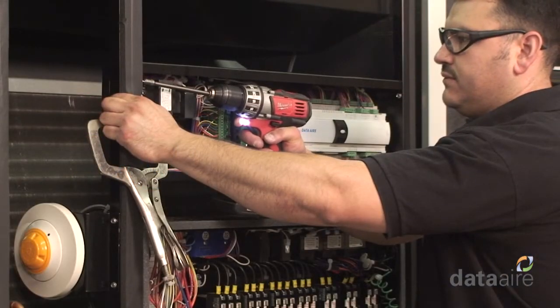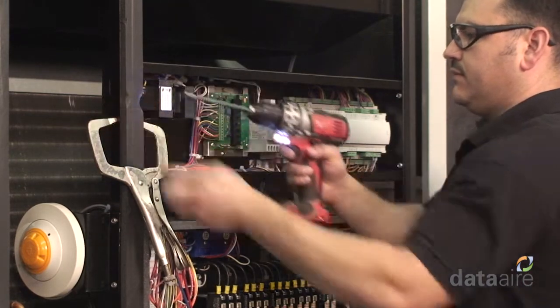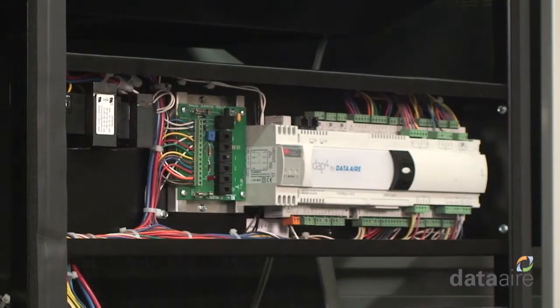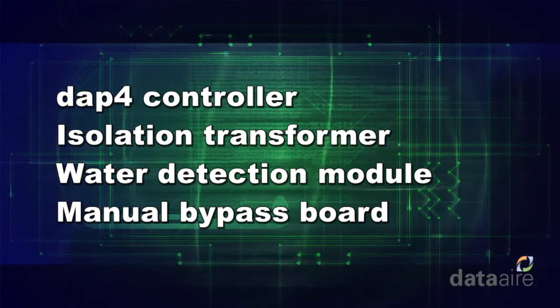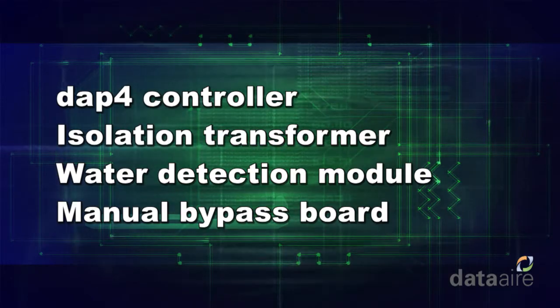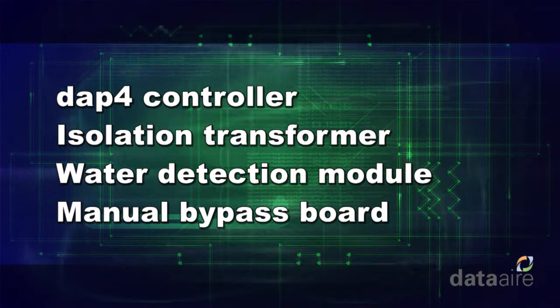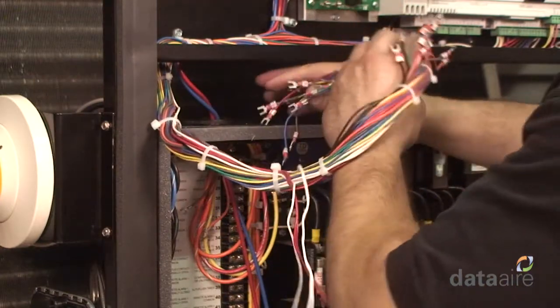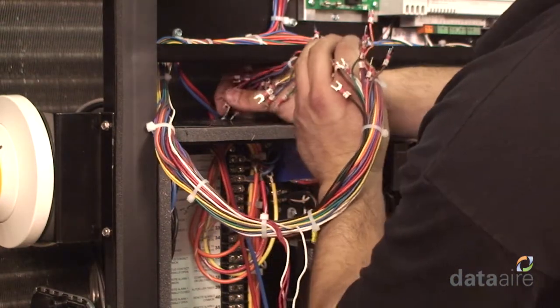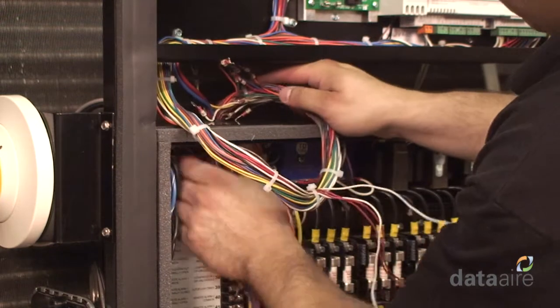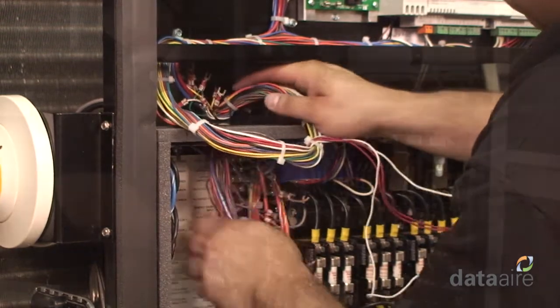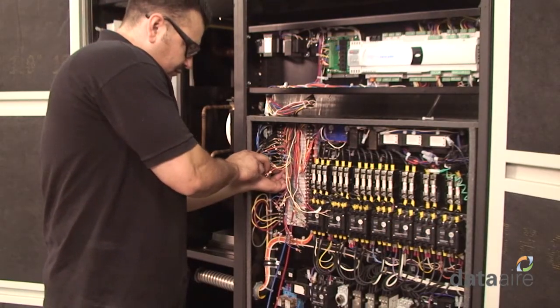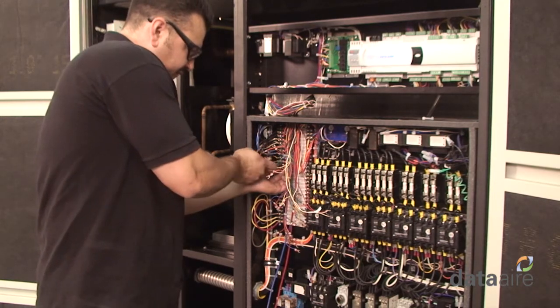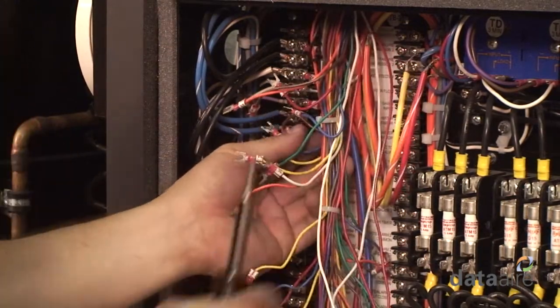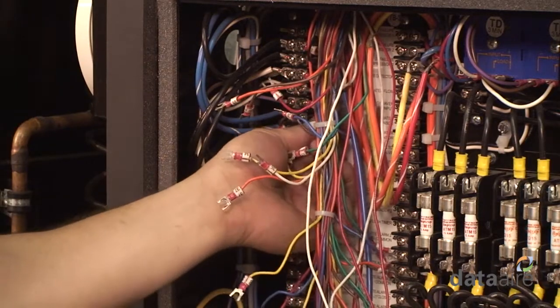The next step is to mount the DAP4 control panel in the same location where the existing DAP panel was located. The new control panel contains the DAP4 controller, isolation transformer, water detection module, and manual bypass board. Route the DAP4 panel's wiring harness through the same opening as the existing controller's cable on the unit's electrical panel. Then, connect the wiring harness to the existing unit's terminal strips. The wire numbers of the DAP4 wiring harness should line up perfectly with the existing terminal strips' pin numbers.